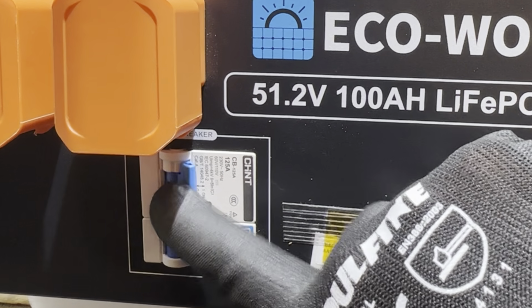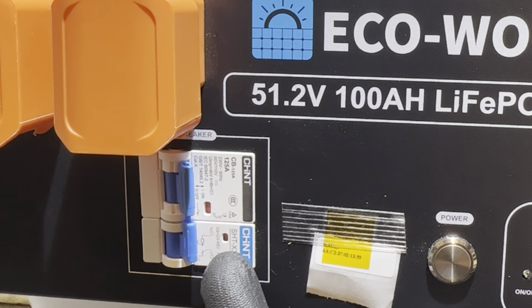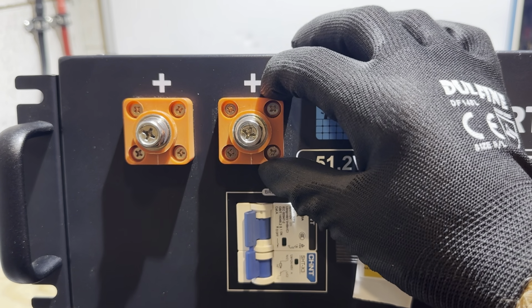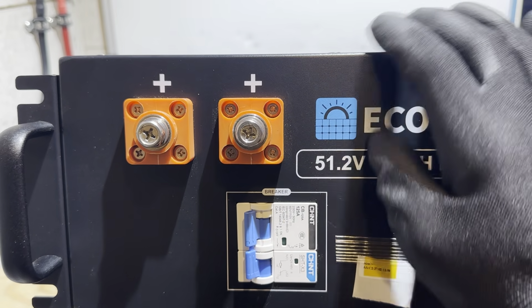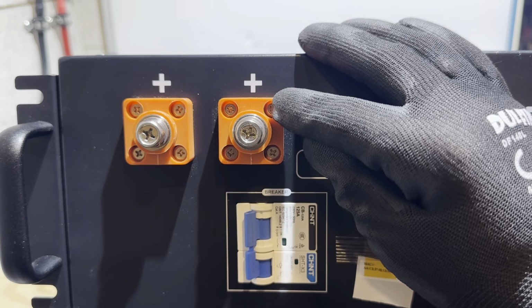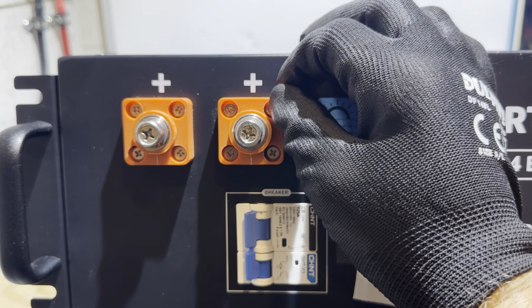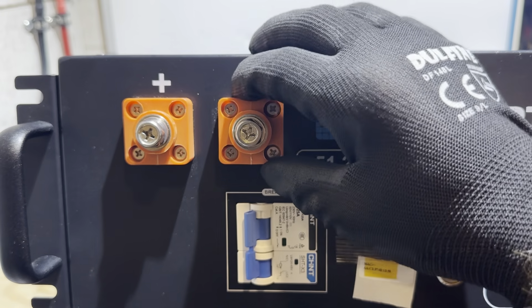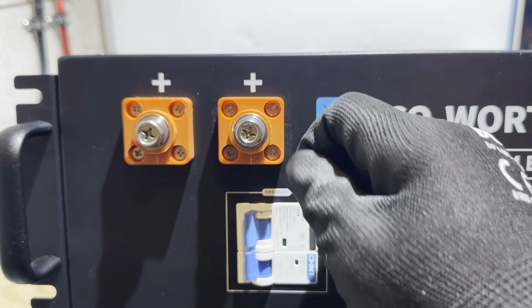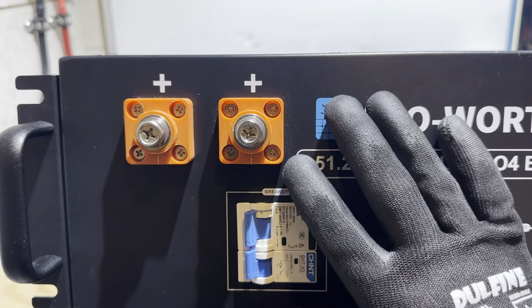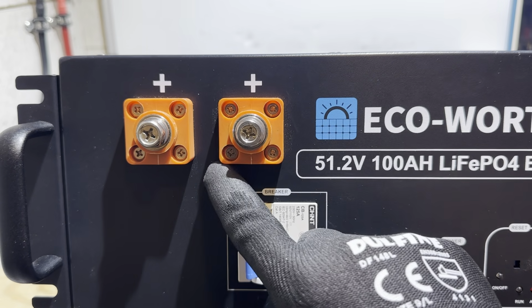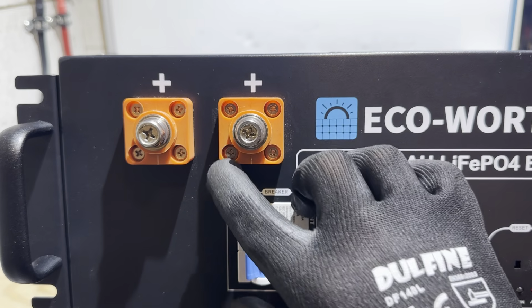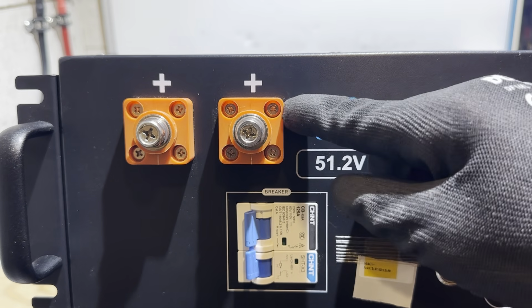The pass-through terminals on version 3 are different than version 2. These are inset, where version 2 had flush mount screws, and there was a potential on version 2 that you could short it if you touched the screws to the case. They took that safety measure into account on this version, so there's no way to really short it out now with the case screws for the pass-through.